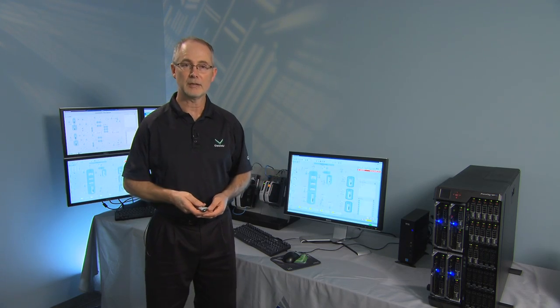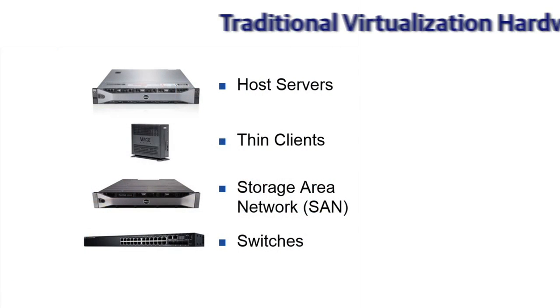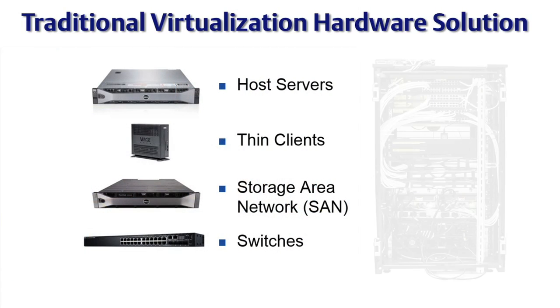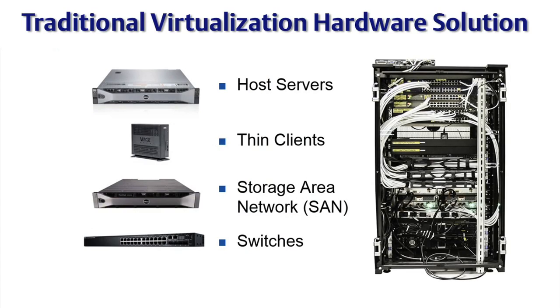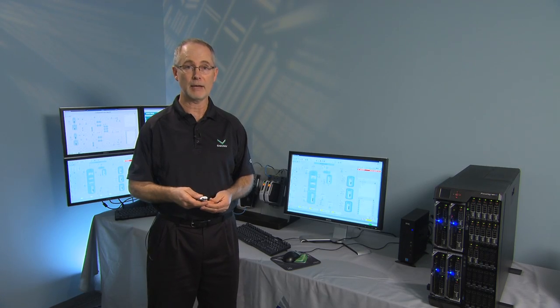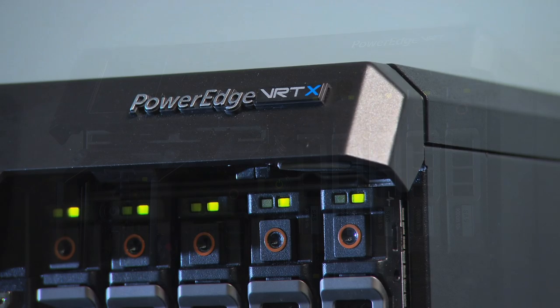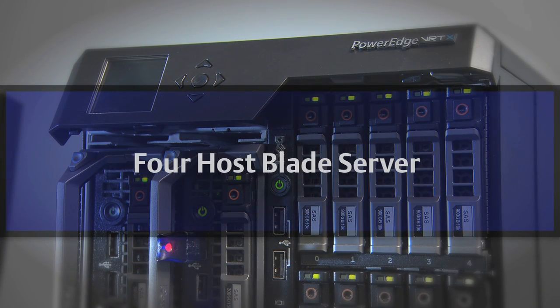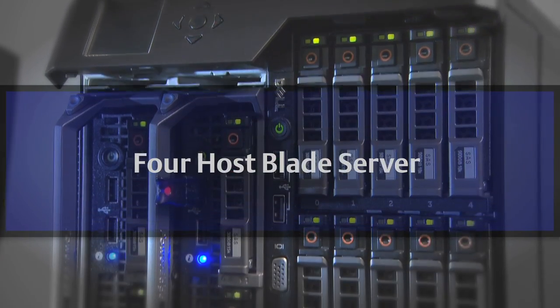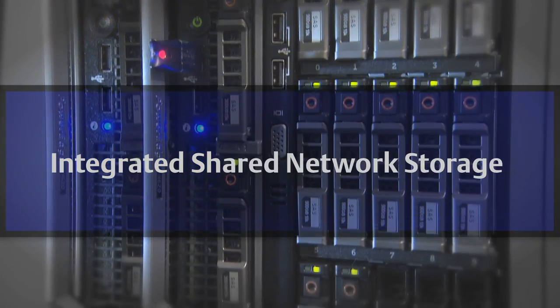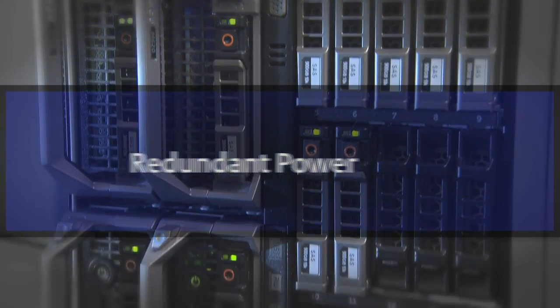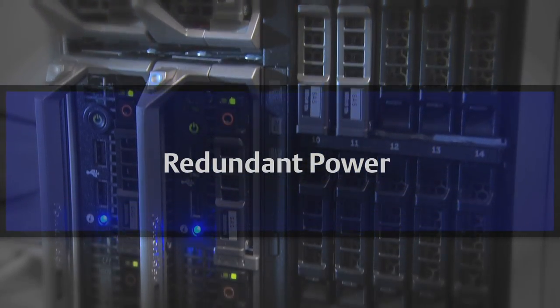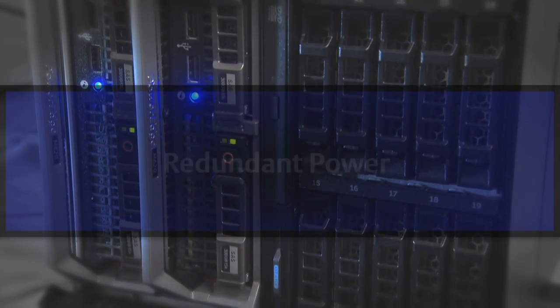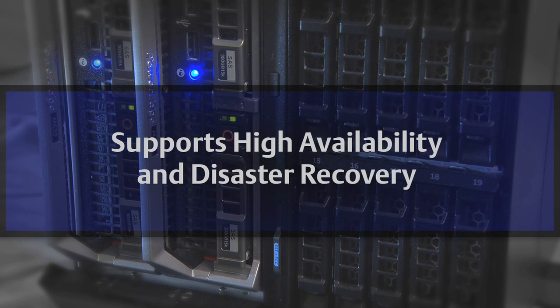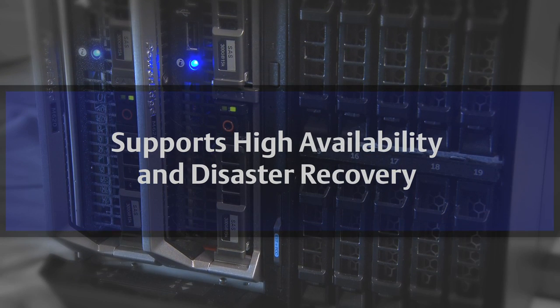In a traditional implementation, you would have separate host servers and switches and SAN devices, typically housed in a cabinet, wired together independently. Now, for an integrated hardware platform for virtualization, we'll be using a blade server. In this case, it's the Dell PowerEdge VRTX, which has 4 integrated host servers, as well as integrated storage area network, switches, and redundant power supplies. This provides a very powerful environment for virtualization, which we'll have fully integrated with DeltaV Virtual Studio, including the high availability and disaster recovery features.